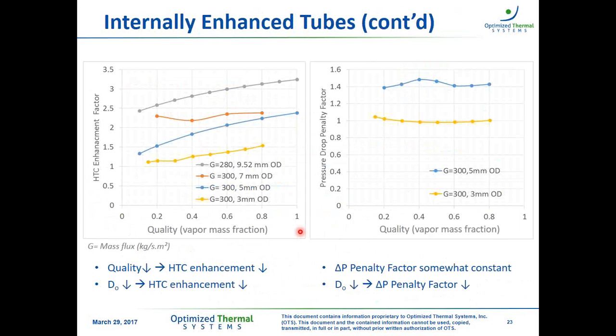Now let's just look at a few numbers. If we look at tube enhancements, on this plot we have heat transfer enhancement factor on the y-axis. On the x-axis we have quality, or vapor mass fraction, and each of these curves indicates a tube diameter, say 3 all the way to 9.5, and the mass fluxes, which are all the same, I think, except for this one. And similarly, we have the pressure drop penalty factor, indicated here on the y-axis of the second plot, also against quality for different tube diameters, in this case for the same mass fluxes.